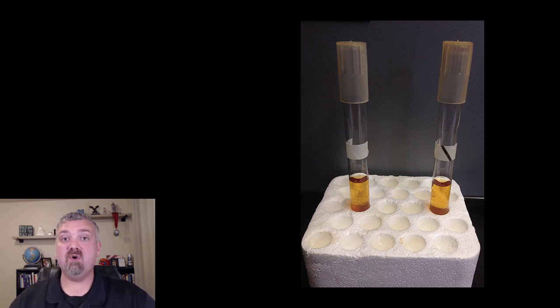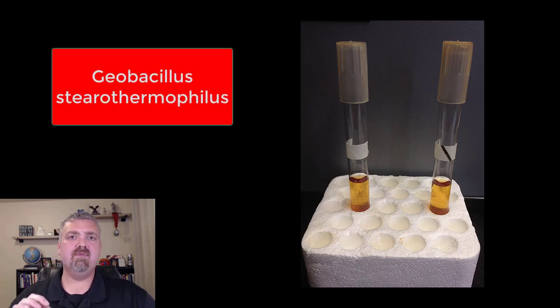Geobacillus stearothermophilus is the best example because it appears to be the most heat resistant spore that we have. So if you can kill those spores in an autoclave, you know you're killing the spores you have to worry about.